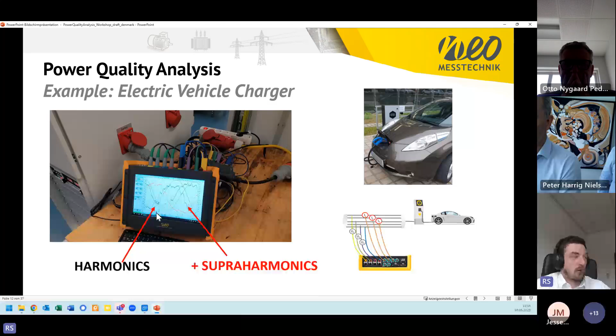So on the one hand side, we have of course also a little bit of harmonic loads, but we see also a lot of supraharmonics. And if we check this in the current FFT, we see the scope waveform of the voltage - a very nice sinusoidal waveform of the three phases. This is everything fine. For the current, we see also quite a sinusoidal waveform, but we see these higher frequency components on the waveform, and therefore in the FFT, for example, marked here as switching frequency at approximately 20 kilohertz.